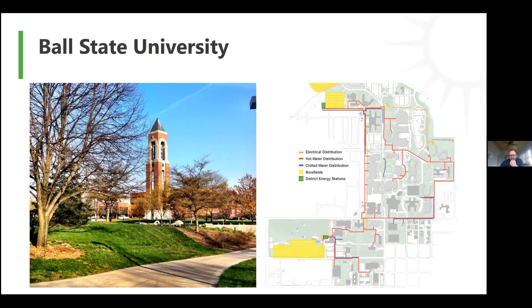So we transitioned the campus to a full 4-pipe distribution system, chilled water and heating water, and derived a large system there. Most importantly, the campus energy use intensity has gone from 175 kBtu per square foot per year down to 105, through implementing the transition from steam to hot water, and then high efficiency ground source heat pumps. We did put 2 new district energy stations in this system, one on the north and one on the south.